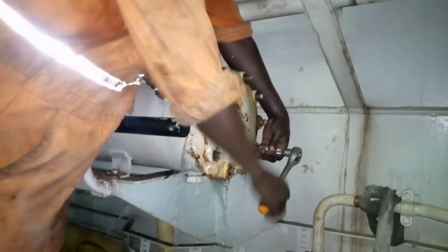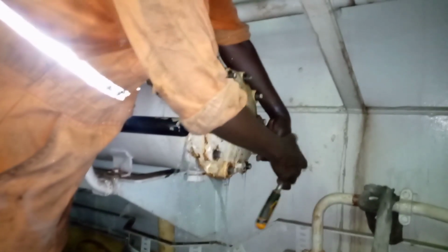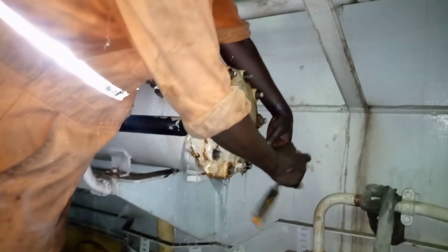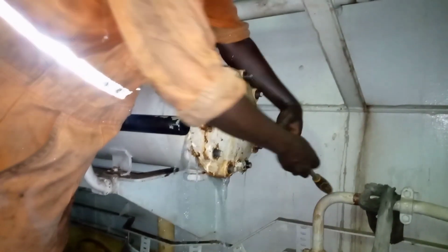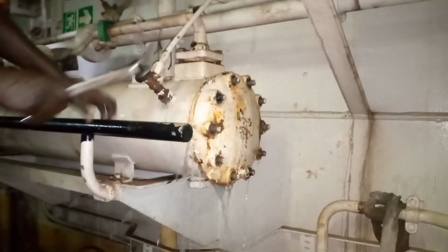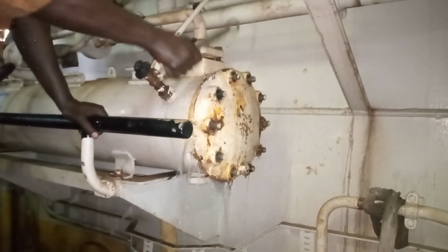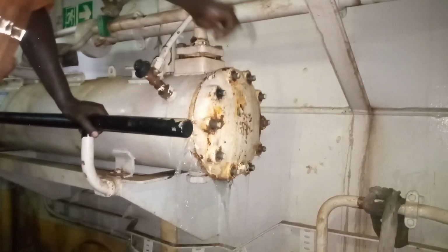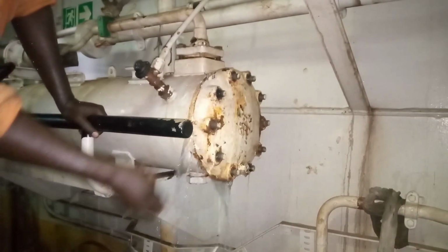Thereafter, we could now start opening one end of the heat exchanger, and as you can see, the ratchet spanner was very helpful to us. The water that can be seen coming out is the water that was already inside the system before we closed the heat exchanger inlet cooling valve.